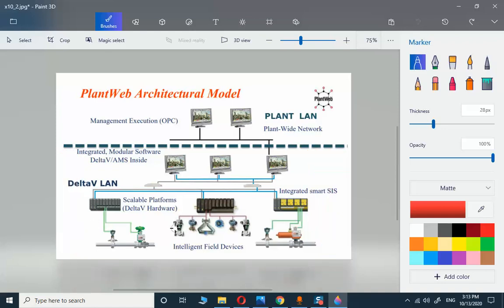We have four types of products in this category. We have the safety PLCs, and we have ordinary controllers with ordinary traditional IOs, like 4-20 milliampere signals to control valves or to bring data from transmitters, and also some switches, lamps, and binary actuators. This part is the most important and the biggest portion of the PlantWeb. We have intelligent field devices, like devices on the Foundation Fieldbus.